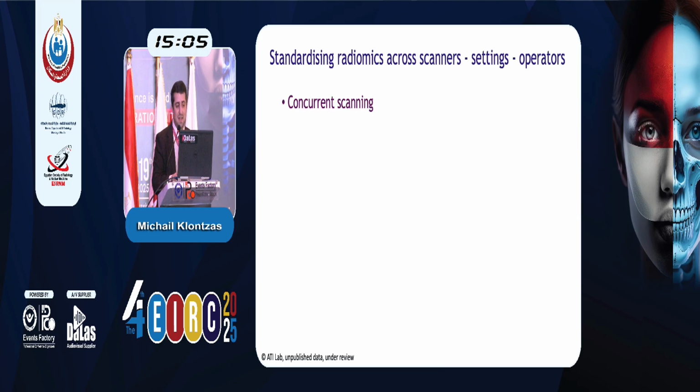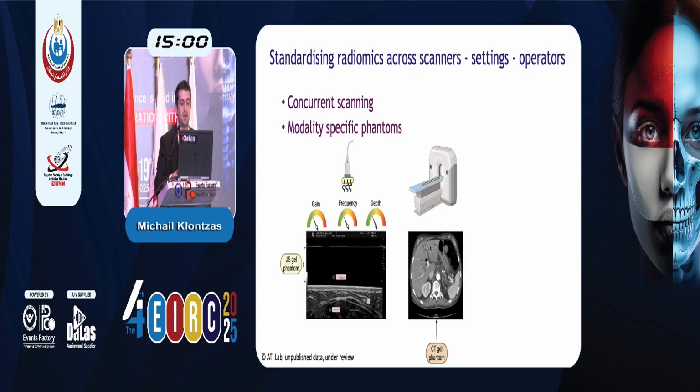The other way we've tried to standardize the method is by doing concurrent scanning with modality-specific phantoms. When I say modality-specific phantoms, we have, in collaboration with our medical physicists, developed phantoms that are specific to ultrasound and CT, and we're now working on an MR phantom. Instead of scanning the phantom separately from the patient, you scan the same phantom every time you scan any patient in your department, and you use the same phantom across different scanners. This will help you reduce the variability, because you scan the same thing every time, even if you have different settings or different patients or different machines.